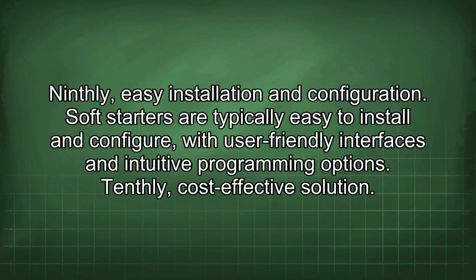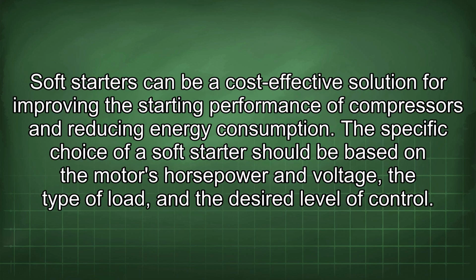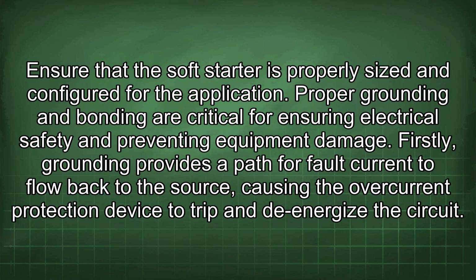Ninthly, easy installation and configuration. Soft starters are typically easy to install and configure, with user-friendly interfaces and intuitive programming options. Tenthly, cost-effective solution. Soft starters can be a cost-effective solution for improving the starting performance of compressors and reducing energy consumption. The specific choice of a soft starter should be based on the motor's horsepower and voltage, the type of load, and the desired level of control. Ensure that the soft starter is properly sized and configured for the application.